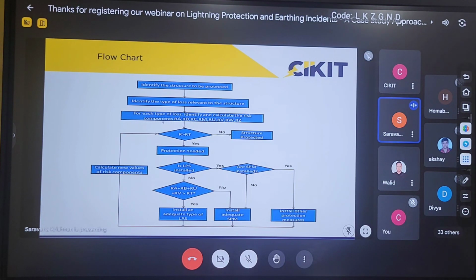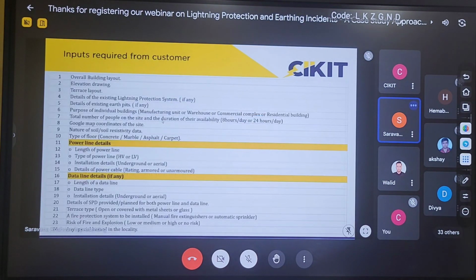For performing this calculation, these are the details which we require from the customer side. First one is the building dimensions, layout details, and whether there is any existing system present or not. What is the level of the system they have installed? What is the purpose of the building? Because if it is a chemical building, the risk of fire exposure will be higher. If it is a residential building, it will be lower. And what will be the total number of people, and the Google coordinates. These are the inputs which we receive from the customers for performing the risk assessment calculations.